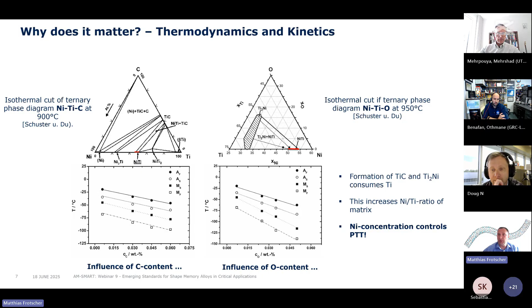Looking at the ternary phase diagrams of nickel-titanium-carbon and nickel-titanium-oxygen, it becomes obvious that Nitinol can dissolve a significant amount of carbon, but forms TiC in the matrix upon solidification. And the diagram on the right shows the same for Ti2Ni being able to dissolve oxygen. That's why it is so important to control both, so that the formation of inclusions is reduced to a minimum, ideally. You can also see that both increasing carbon and oxygen content shift the phase transformation temperature downwards. The reason is that titanium is consumed during the formation of these secondary phases, and thus the nickel content in the matrix increases. So it is not just about fatigue, but also about achieving your desired phase transformations for the application you have in mind.